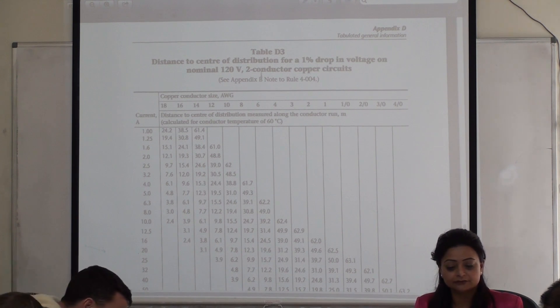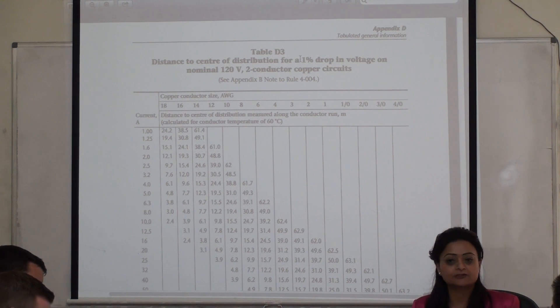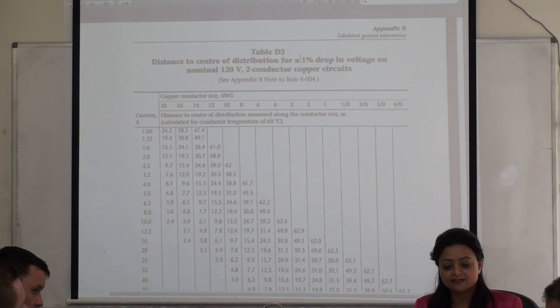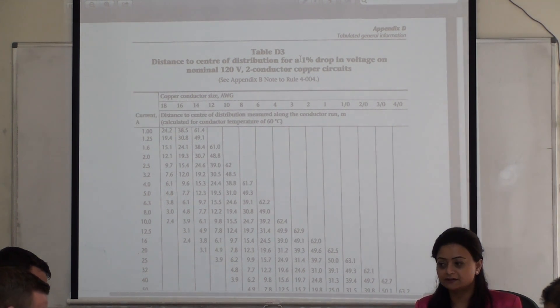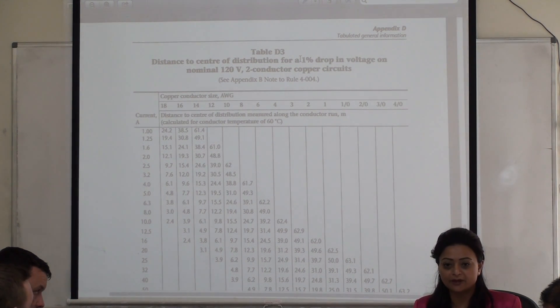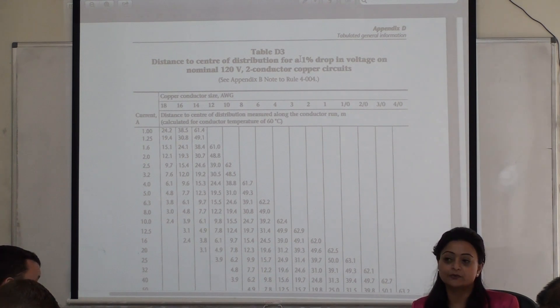Table D3 is designed to calculate, let's say from pole to the plug, how much drop is allowed — and that's 5%, right? So the question is: while installing a 240-volt supply and the load is located 127 meters away, what shall be my minimum gauge wire size needed for a 3% voltage drop, such that my breaker size is 40 amps? You're going to practice this question in detail.